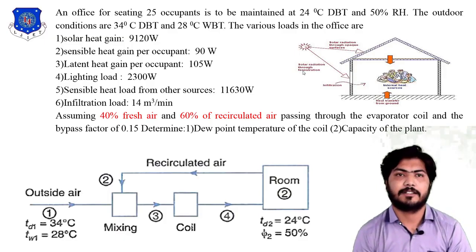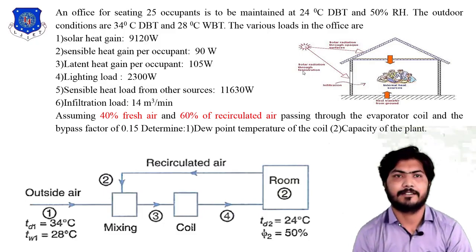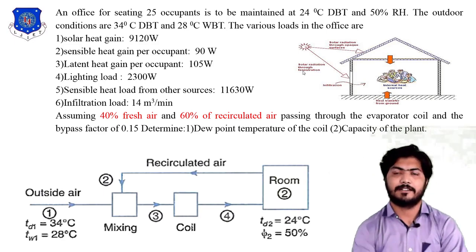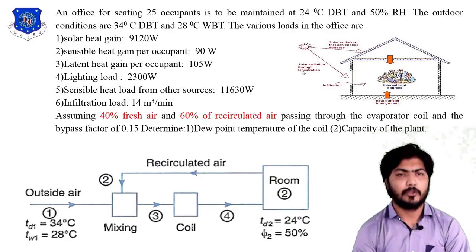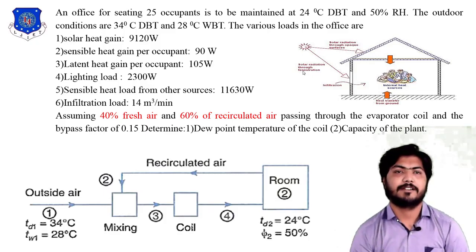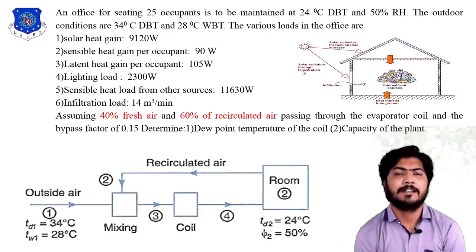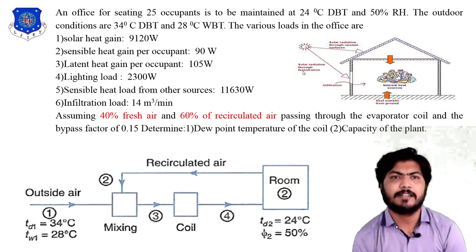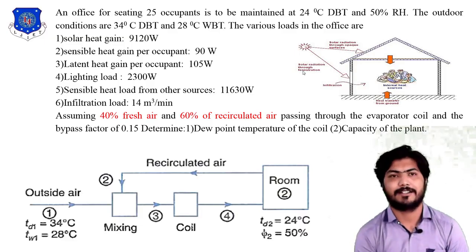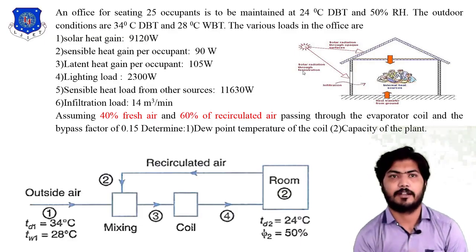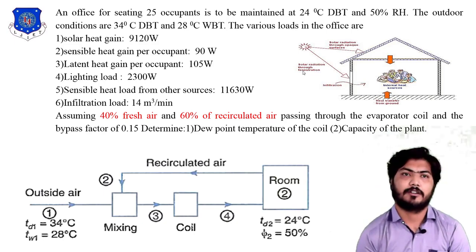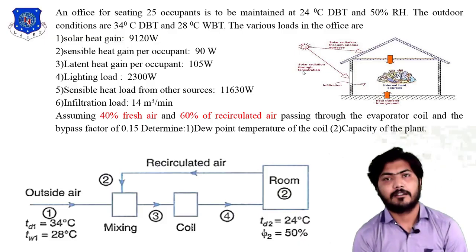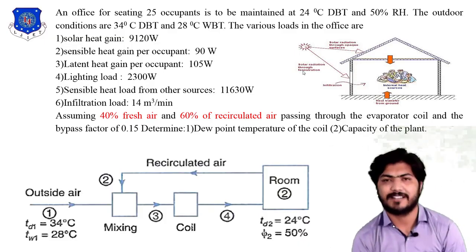First, the outside conditions and inside conditions to be maintained are given. We draw these on the psychrometric chart: the outside condition is point 1 and the required room condition is point 2. To locate point 1, the dry bulb temperature is a vertical line on the psychrometric chart. The inclined wet bulb line and the vertical dry bulb line are crossed to give the intersection point, which is the outside air condition point 1.